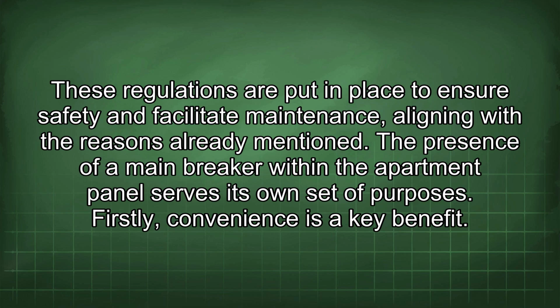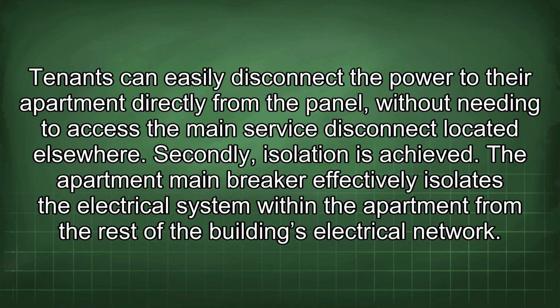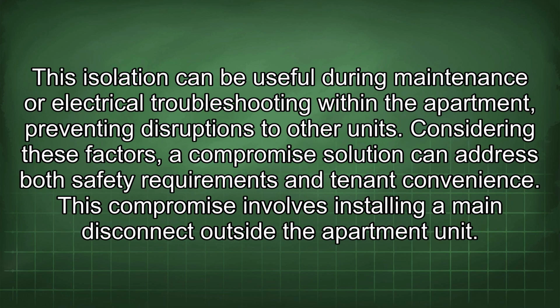The presence of a main breaker within the apartment panel serves its own set of purposes. Firstly, convenience is a key benefit. Tenants can easily disconnect the power to their apartment directly from the panel without needing to access the main service disconnect located elsewhere. Secondly, isolation is achieved. The apartment main breaker effectively isolates the electrical system within the apartment from the rest of the building's electrical network. This isolation can be useful during maintenance or electrical troubleshooting within the apartment, preventing disruptions to other units.